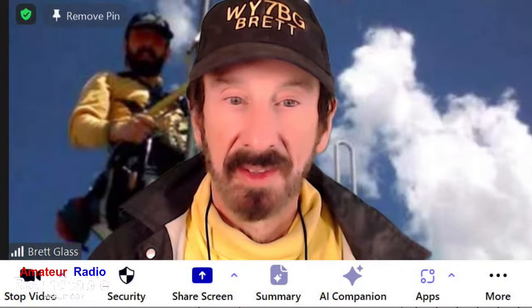Brett, do you want to discuss the difference between bonding and grounding, because it is in the electrical code? Well, people make a big fuss about it, make it really complicated. Grounding means connecting things to your ground system, and bonding means connecting all those things together, basically, in one sentence. You don't have separate grounding systems. You can have multiple ground rods, you can have a fancy multi-point grounding system, but in the end, everything has to be bonded together for it to be safe, because otherwise you can get potential differences, as Tom was mentioning, between one part and another, and that's when you can really get into trouble. Everything has to go back to that intersystem bond. Everything in your station goes back to that.